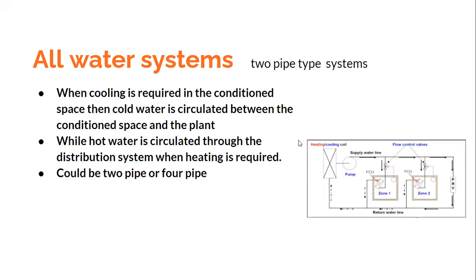Okay, conditioning plant. There could be a 2-pipe system. Now this is a 2-pipe system, or there could be 4-pipe systems. So if you want exclusive cold water pipes and hot water pipes, then you need to have a 4-pipe system. If you want to use the same pipe for heating and cooling, then it has to be a 2-pipe system. Okay, so very simple to understand.